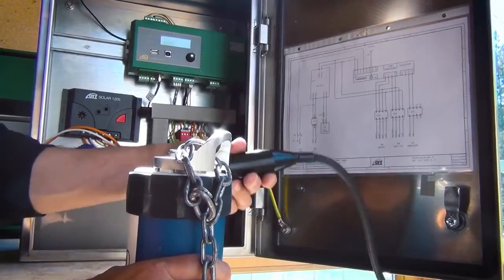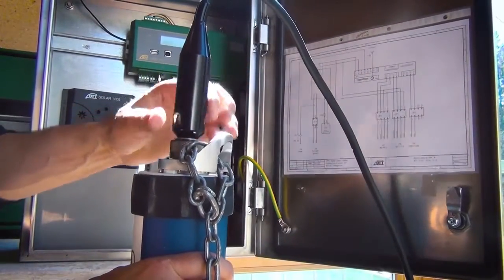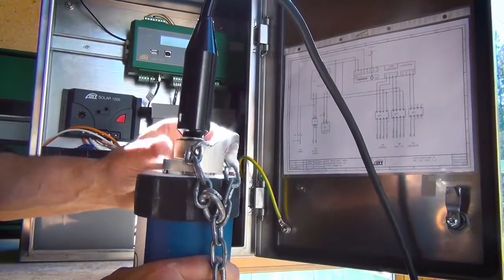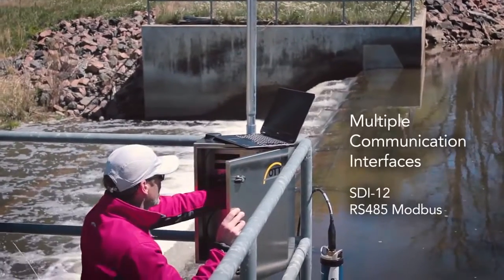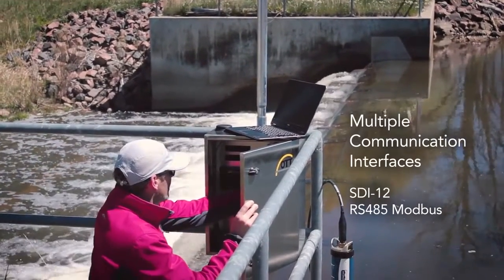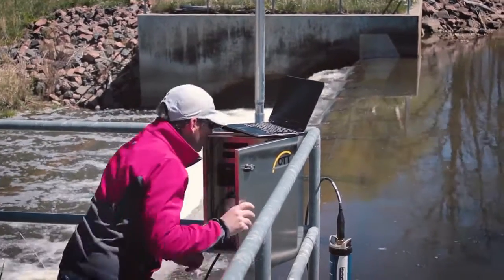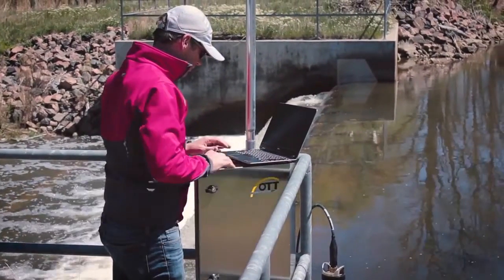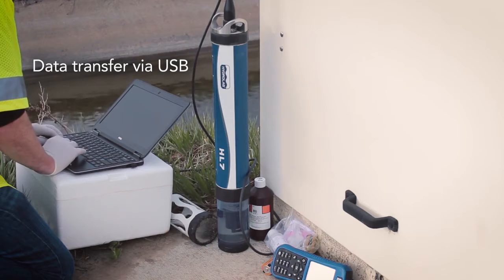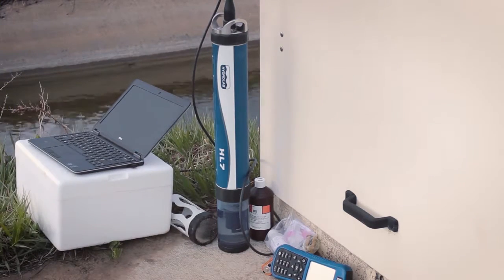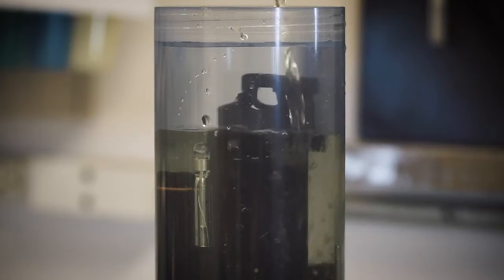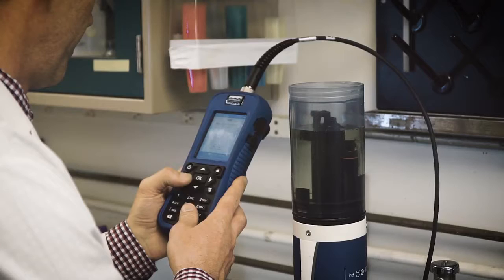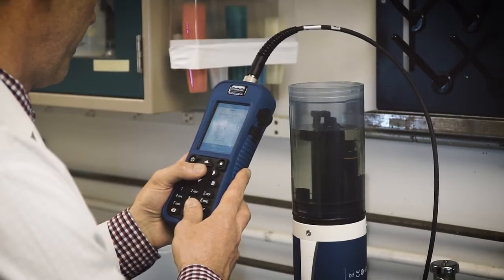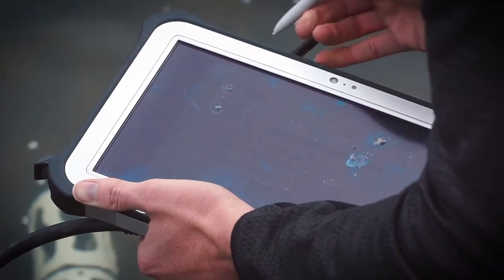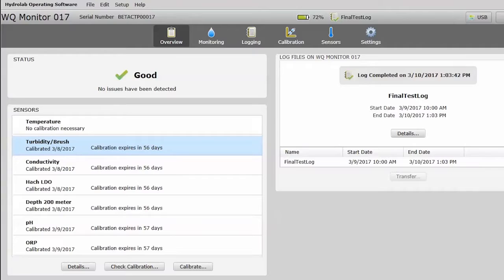The HL7 also offers faster integration to data loggers and data acquisition systems with multiple communication interfaces, including SDI-12 and RS-485 Modbus communications, and quick data transfer via USB to rugged field laptops. You can view data, store, calibrate and configure HYDROLAB sondes with the handheld surveyor HL, or view on a tablet or rugged laptop using the simple and intuitive guided software.